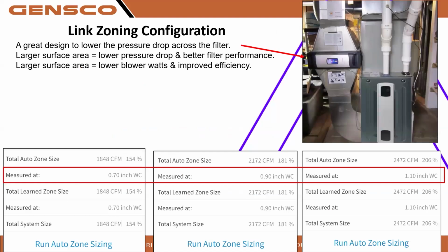We just added this one in. This is an S8V2 Lynx furnace. This is a great picture of ductwork. Please, please, please build a transition to try to get as much of that filter as possible. It's really bad when we see these plenums come straight down and we're panning off 4 to 6 inches of that air filter. We're restricting airflow and we're not actually using that filter to its best.